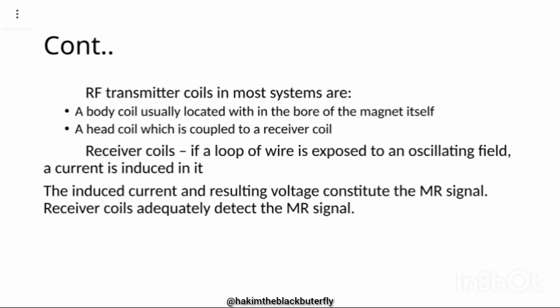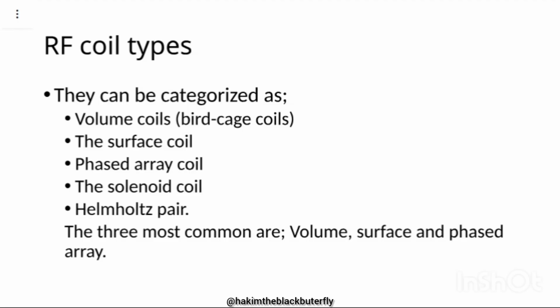Then receiver coils. If a loop of wire is exposed to an oscillating field, a current is induced in it, and what is causing the oscillation is the RF pulse. The induced current is now going to be the MRI signal, and the resulting voltage constitutes the MRI signal. So the receiver coils adequately detect the MRI signal. The transmitter brings the RF, and the receiver coils are available to pick up that particular signal that is being induced because of the change in the magnetic flux.